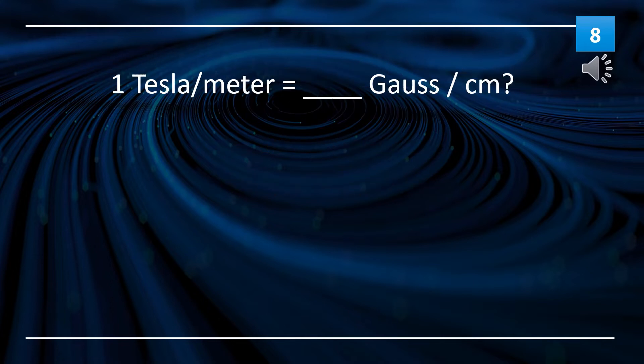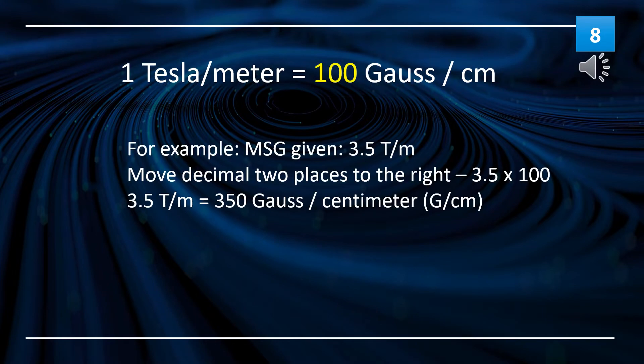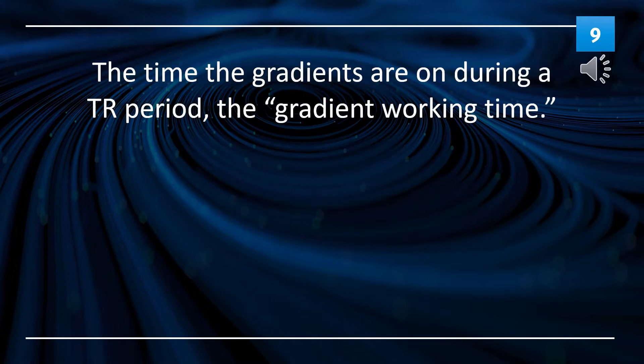One tesla per meter equals how much gauss per centimeter? One tesla per meter equals 100 gauss per centimeter. The time the gradients are on during a TR period — the gradient working time — is defined as duty cycle.